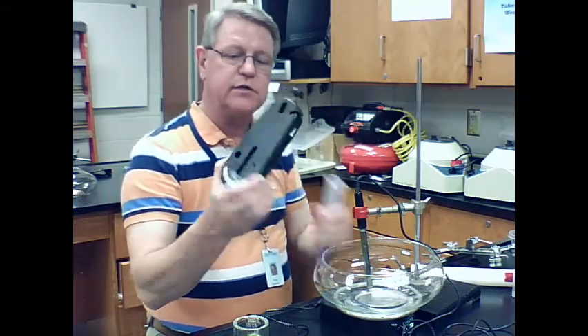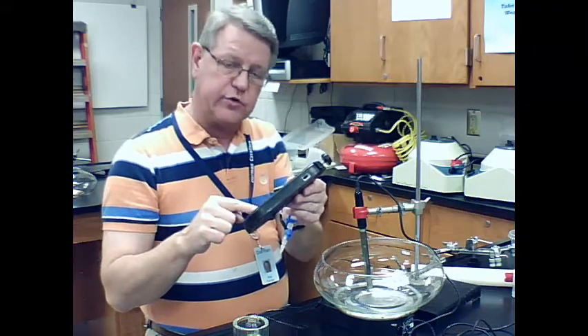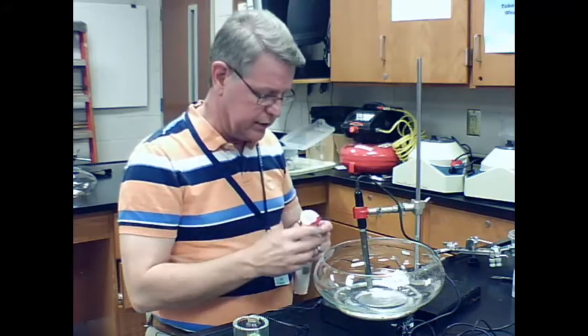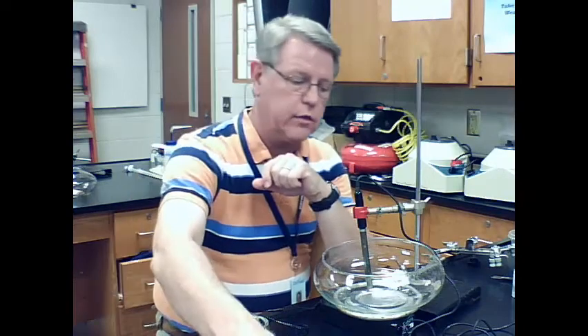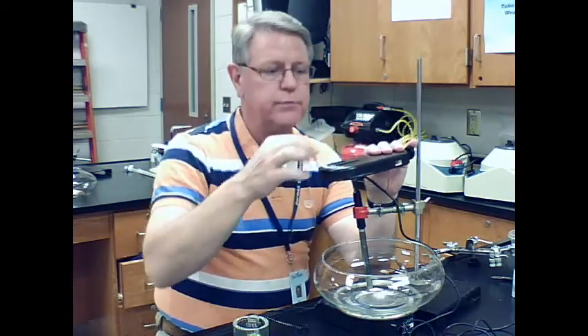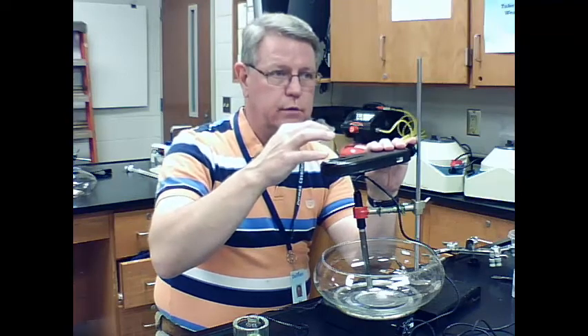really careful with it to allow those drops to fall through here so they don't strike the sides. Once it strikes the sides, that solution will get into the electronics and will mess them up, and so eventually it'll stop working, and they're kind of expensive to replace, so you need to be very careful about that. If you're going to use the drop counter, you have to calibrate the drop counter.